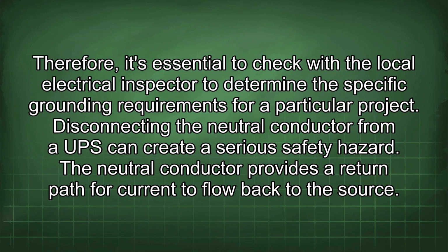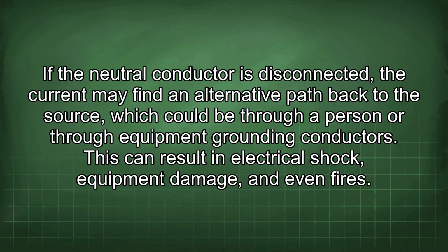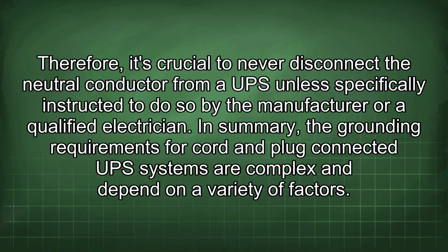Disconnecting the neutral conductor from a UPS can create a serious safety hazard. The neutral conductor provides a return path for current to flow back to the source. If the neutral conductor is disconnected, the current may find an alternative path back to the source, which could be through a person or through equipment grounding conductors. This can result in electrical shock, equipment damage, and even fires. Therefore, it's crucial to never disconnect the neutral conductor from a UPS unless specifically instructed to do so by the manufacturer or a qualified electrician.